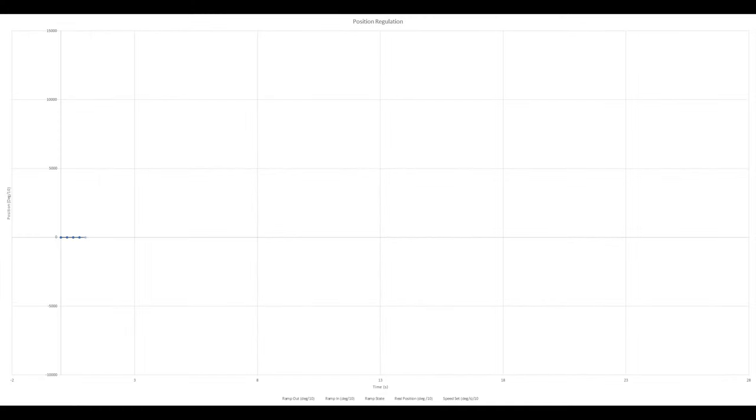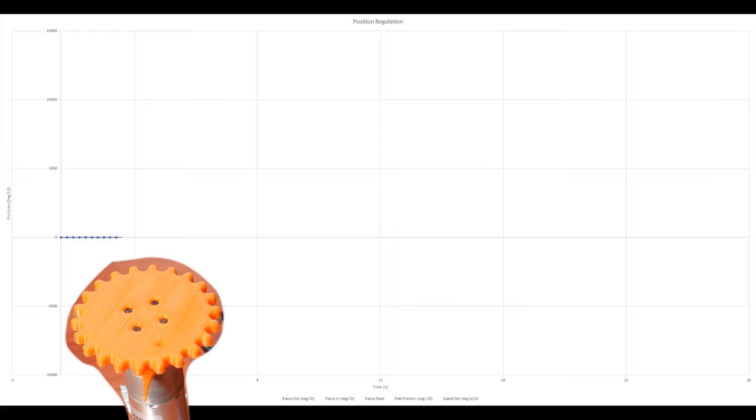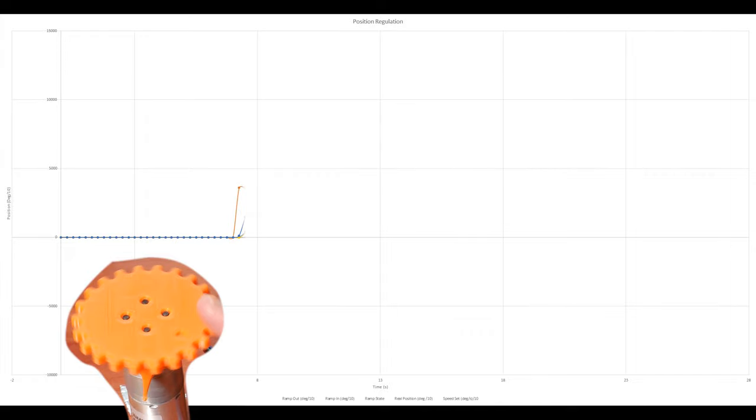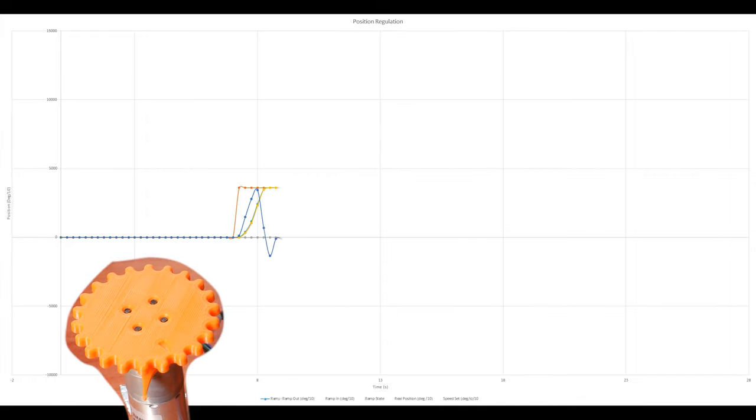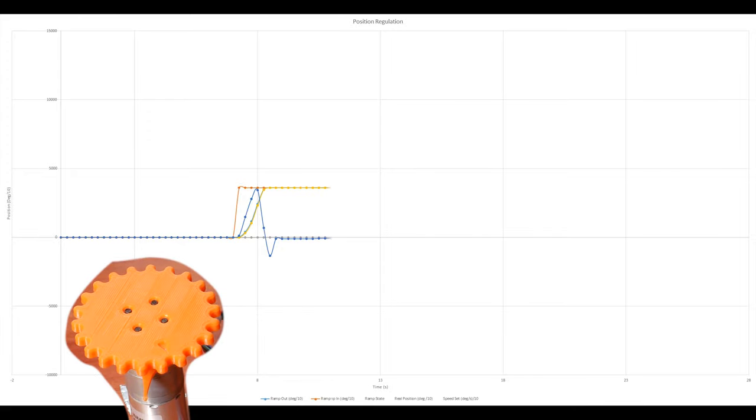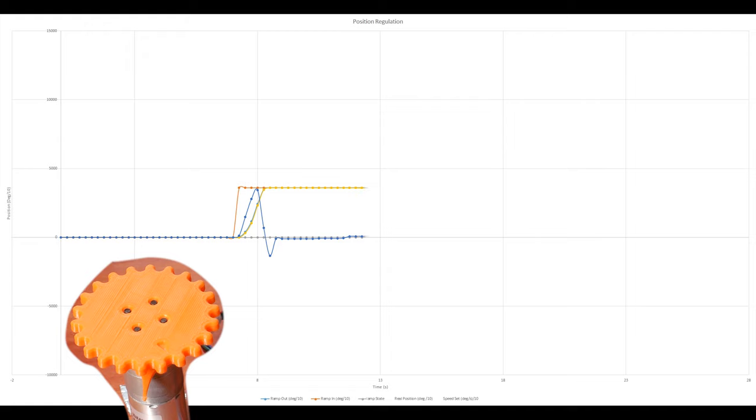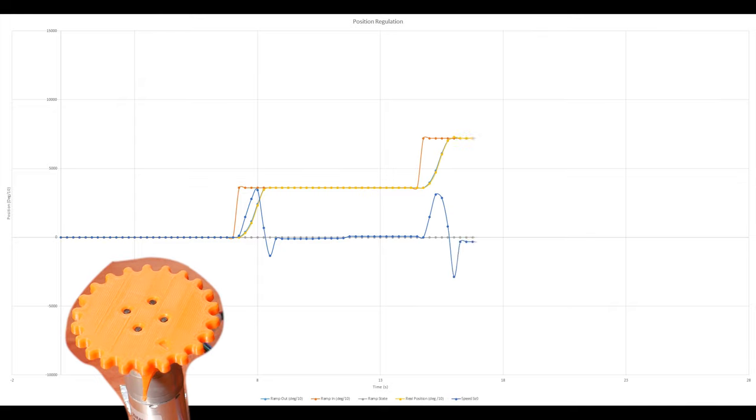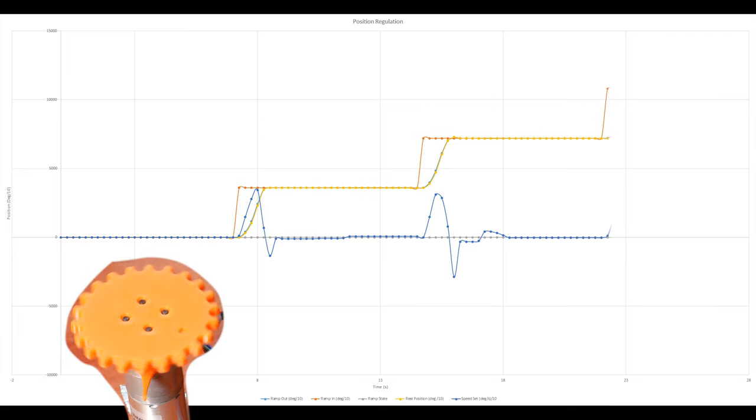There are a few critical things that I want you to see in this graph. First of all, ramp out and ramp in. Ramp in shows the requested position. This is where you see that step function. These are plotted every quarter of a second. That's shown in orange. Then in blue is the output of the ramp generator. Make sure that you're looking at light blue. And it was very, very close with that yellow line. The yellow line is the real position of the motor. It's trailing that output of the ramp generator ever so slightly because, of course, with a PI regulator, there needs to be error for there to be a response. And that's the amount of error as it's chasing that position.